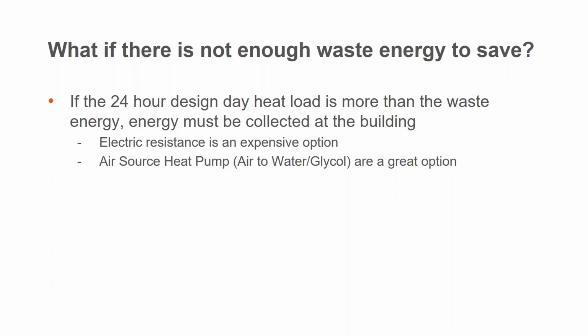There's lots of ways to melt ice to store it. You could do electric resistance if you want. You could have an air coil outside. You could use air source heat pumps. You could have solar collectors, low temperature solar collectors. All they're trying to do is melt ice. So there's a lot of ways that you can melt that water other than just reject heat from the core of the building.